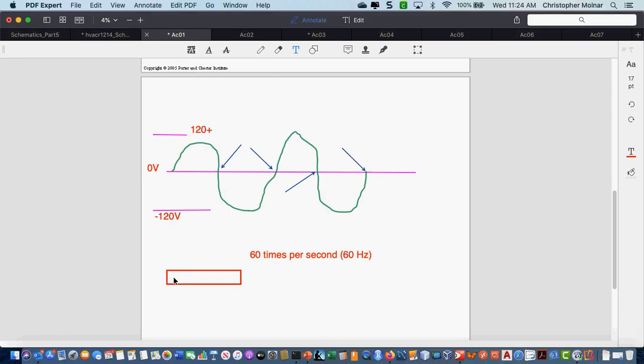One side of this magnet is north, one side of this magnet is south. Now, a motor is built with magnets in it. The motor itself has magnets in it pre-manufactured at the factory. Magnets have a north and a south pole. This is what causes the motor to start spinning: as I'm building a magnetic field in here, all of a sudden I might have a north field. 60 times a second, that changes to a south, and then back to a north. Also, this magnet in the motor is spinning. So I have two rotating magnetic fields.